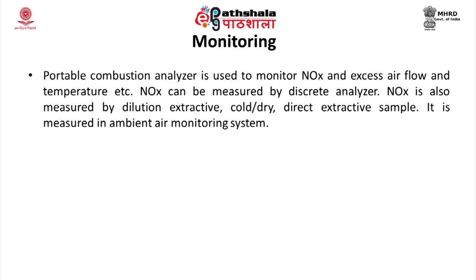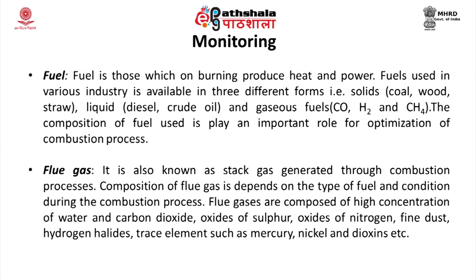Conventional flue gas analysis is used by power plants to optimize the fuel-to-air ratio. The amount of excess oxygen and carbon monoxide in the flue gas, and the least amount of NOx and other greenhouse gases, is measured by the analyzer. The stoichiometric point is where all the fuel has reacted with the available oxygen in the combustion air and no fuel or oxygen is left over.